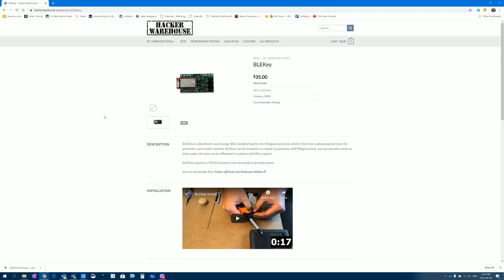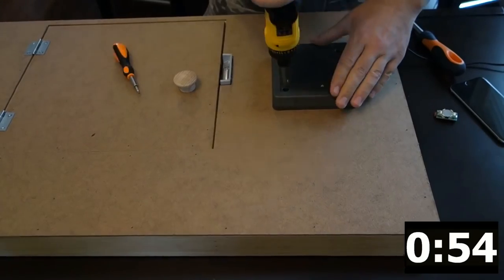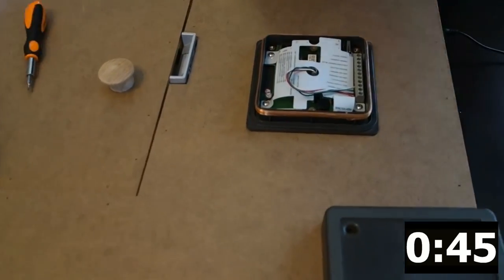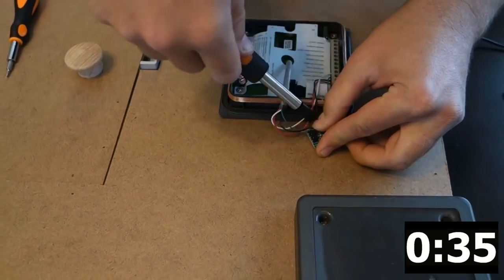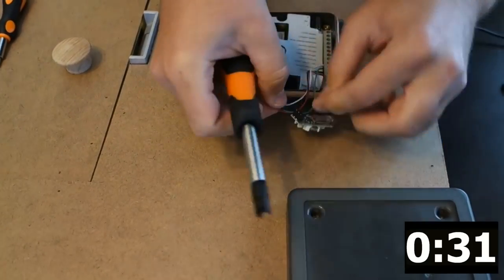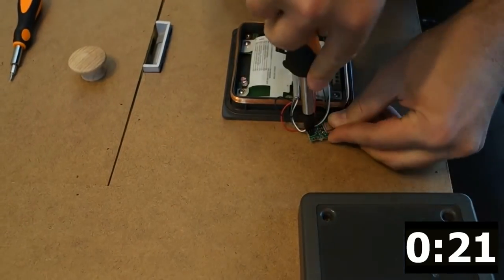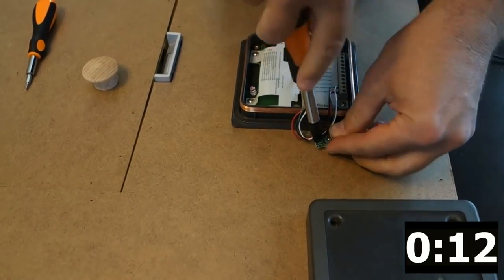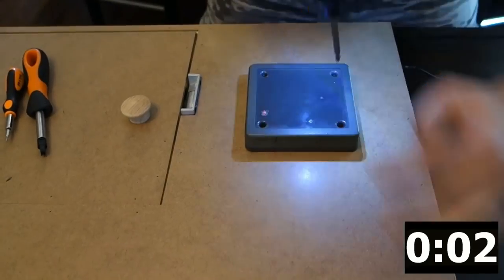So really what you can do is you can pull a reader off the wall. With Wiegand, typically nobody wires the tamper wires, so nobody knows that that reader is being pulled off the wall from a centralized management point through Synergist, let's say. And they'll punch down this little tiny sniffing device that can read the data going across the Wiegand wires. So it's really just zeros and ones, it's bits. And that device has Bluetooth low energy on it. It can connect to a phone, and you can see that data go through in real time.